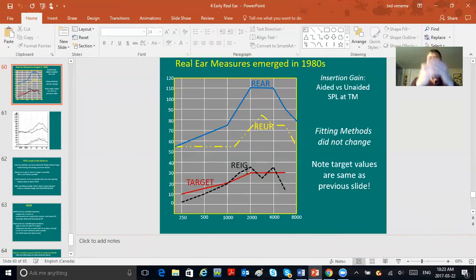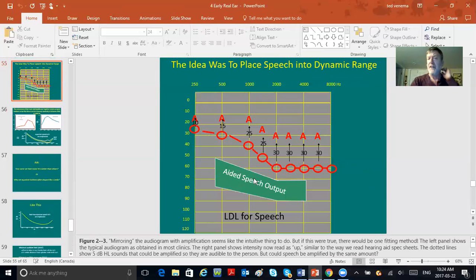Look at REUR — is it used during the hearing test? No, because you're plugging up the ear with a headphone. As soon as you cover the ear with a headphone or jam an insert headphone into the guy's ear, REUR is dead. So if you didn't use REUR in your hearing test, why are you using it in your hearing aid test? The only reason you'd ever want to keep REUR is if you were testing in a sound field — like having the guy raise his hand for tones from speakers. Then your REUR is valid. But if you're jamming an insert headphone in the ear canal, you've ruined that REUR.